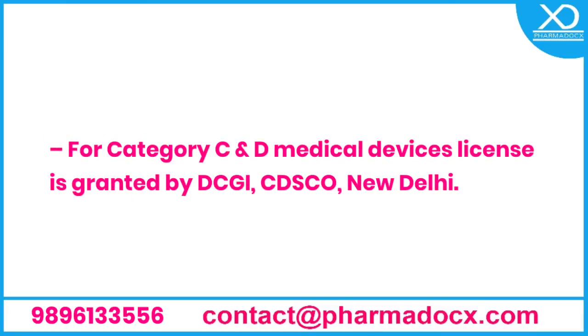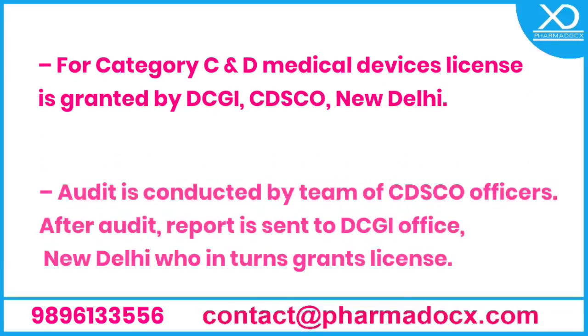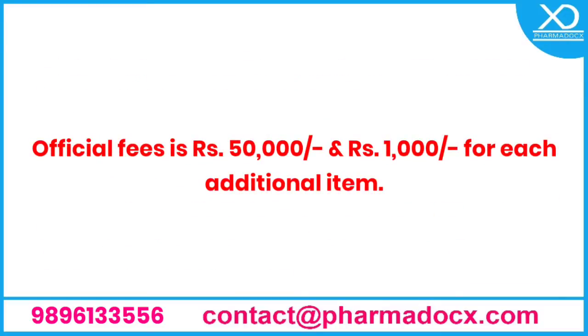For category C and D medical devices, the license is granted by DCGI, CDSCO, New Delhi. The audit is conducted by a joint team of CDSCO officers. After the audit, the report is sent to the DCGI office, New Delhi, by the inspecting drug inspectors, and the DCGI office issues or grants the license. The official fees for C and D category license, which is critical, is rupees 50,000, and there is an additional fee of rupees 1,000 per product.